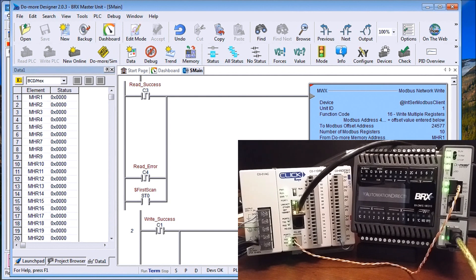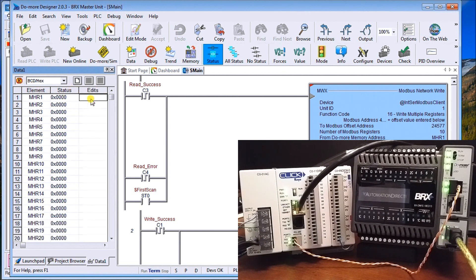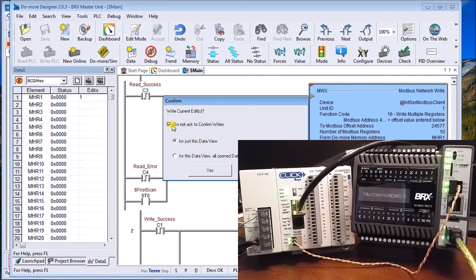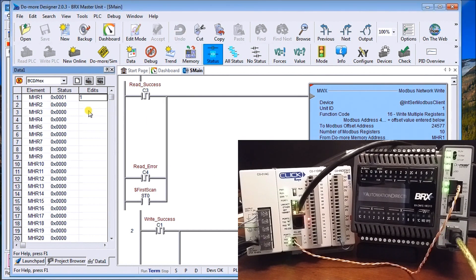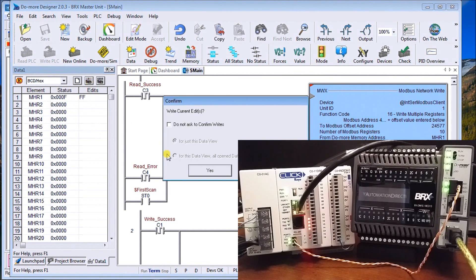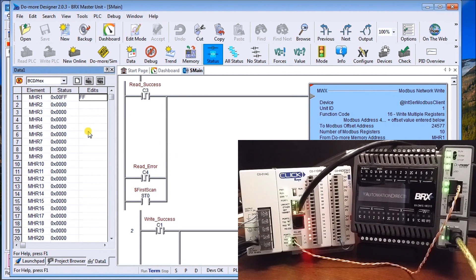Looking at the BRX data view, we're writing some channels. Looking at the very first channel MHR1 — let's change that and put the value of 1 in and write it. You'll notice the first bit on our Click turns on. If we put the value F in there, the first four outputs turn on. Adding values for the next four as well — you can see we are communicating from the BRX over to our Click.